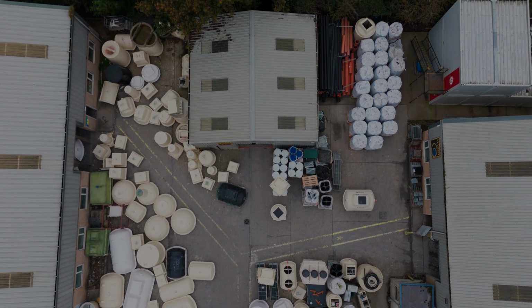Well, the standard that we have to acquire in the UK is a standard called EN or BS-EN 12566 Part 3, which means drainage. Now that has served us very well for nearly 24 years. But recently, a requirement has been asked for by Natural England and also the regulators, not only to hit that standard, but also to bring in what they call nutrient neutrality. And that requires phosphate and nitrate to be reduced substantially from what has been the normal practice. The level of phosphate coming out of a sewage treatment plant was between 6 and 8 milligrams per litre. Now, Natural England set a requirement to reduce that substantially. To be honest, none of us, even Natural England, knew how that would be achieved.